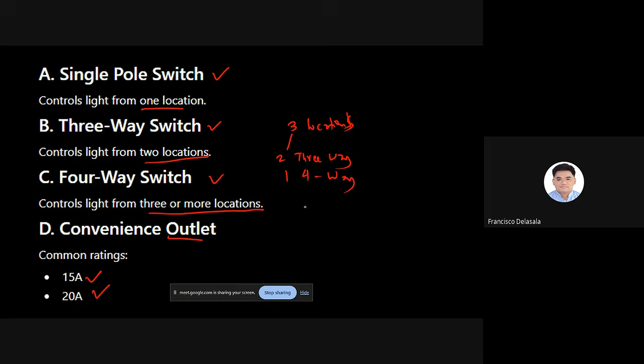If you have gone to our training during our wiring, we know that when there are three locations, the two of them are automatically three-way, and the remaining one will be four-way. So for example, if the question is about controlling a light in 25 locations, the two are automatically three-way, and the remaining 23 will be four-way. Meaning, if you are going to control switches in three or more locations, you always have two three-way switches and the rest are all four-way.